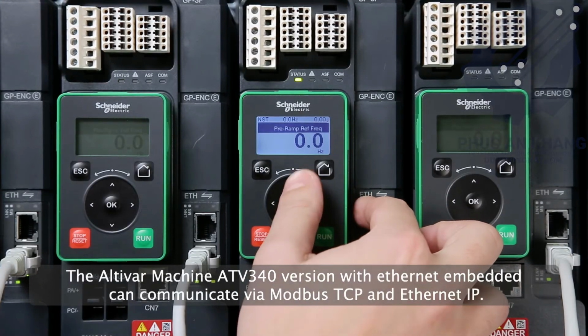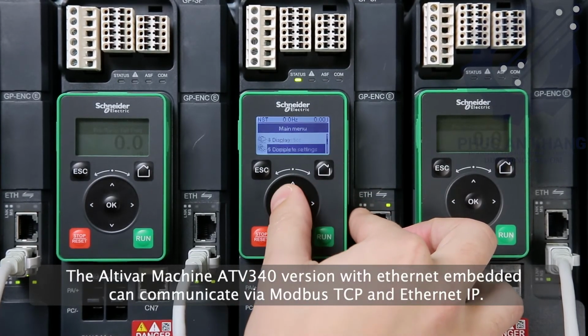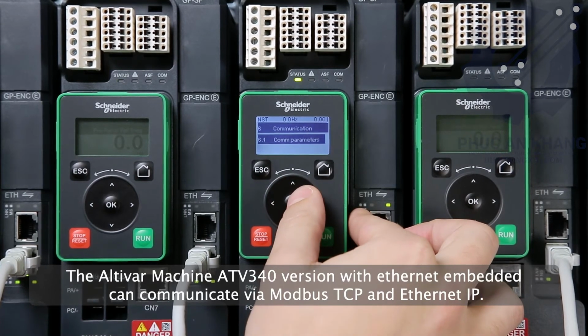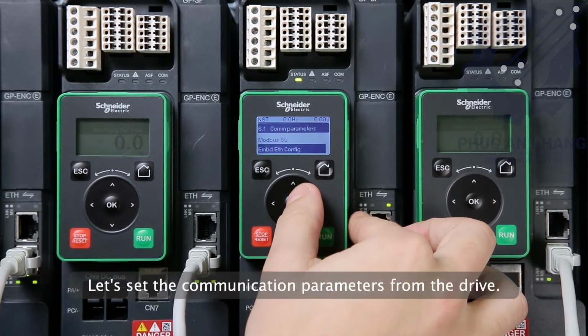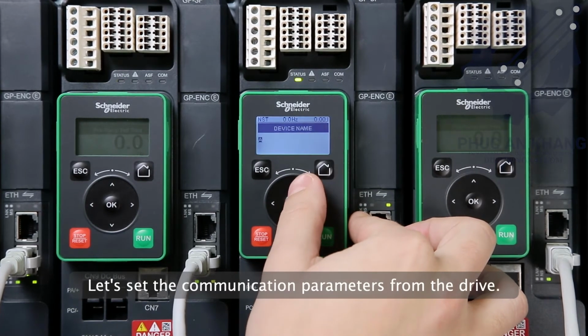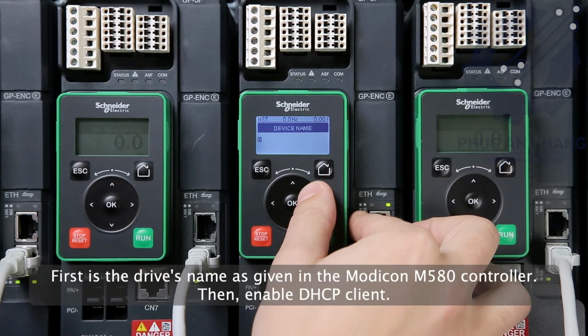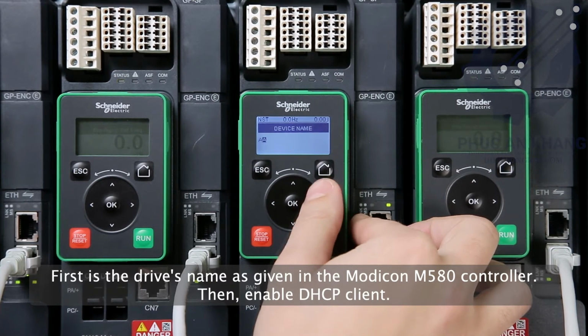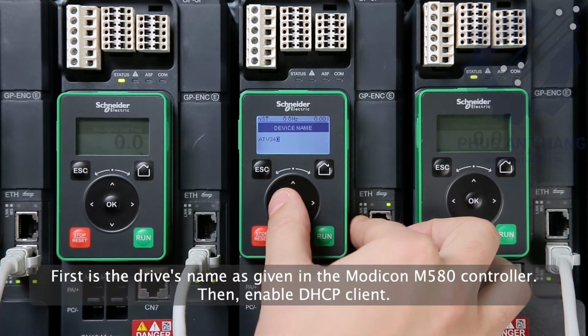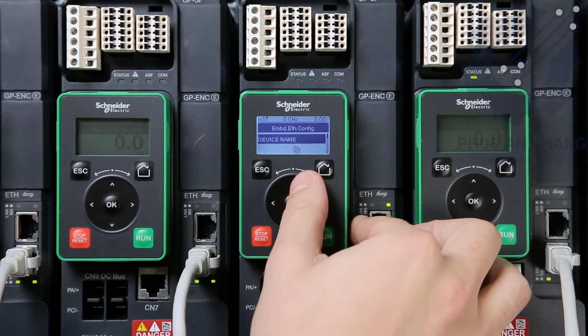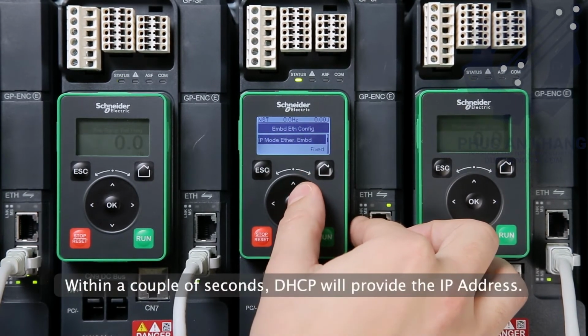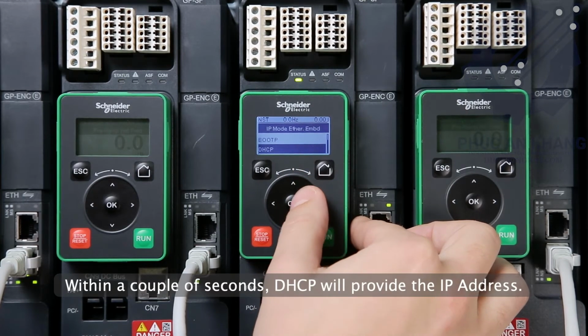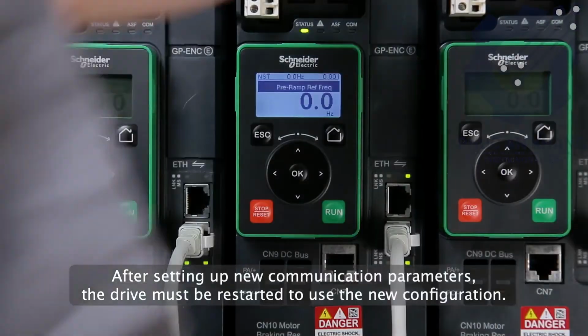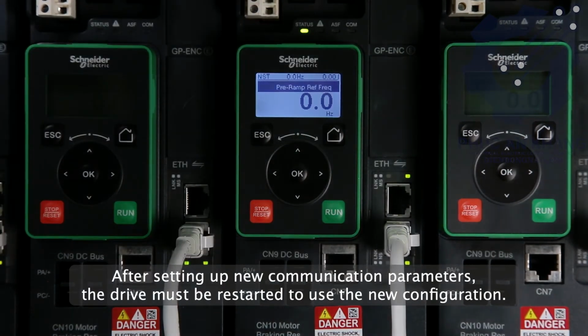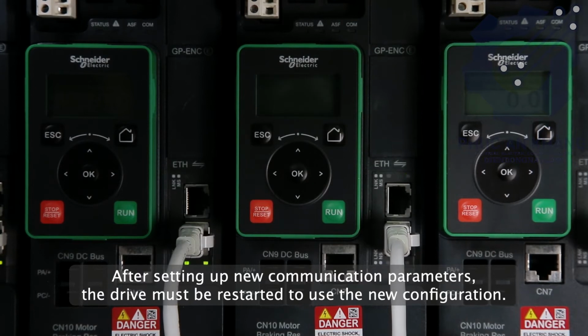The Altivar Machine ATV340 version with Ethernet embedded can communicate via Modbus TCP and Ethernet IP. Let's set the communication parameters from the drive. First is the drive's name, as given in the Modicon M580 controller. Then, enable DHCP client. Within a couple of seconds, DHCP will provide the IP address. After setting up new communication parameters, the drive must be restarted to use the new configuration.